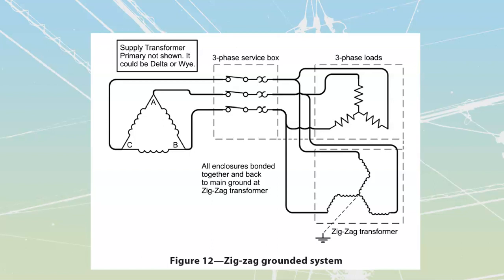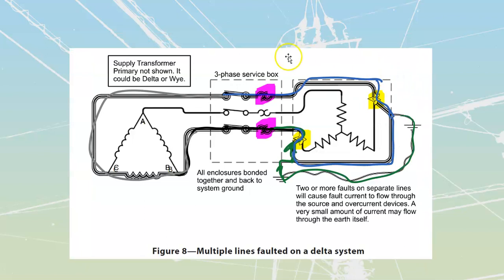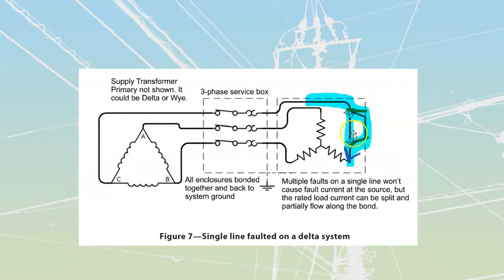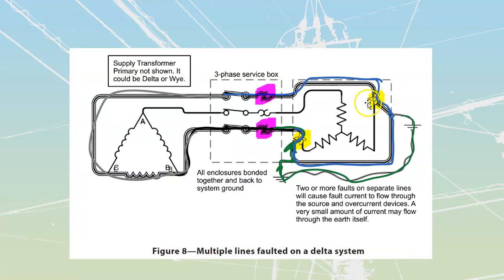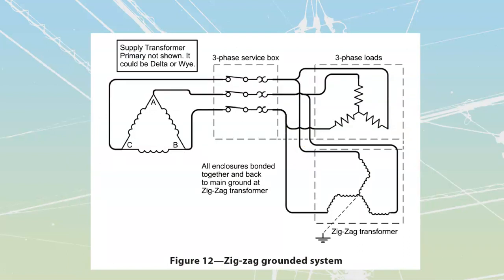Remember how with the delta system before, we said we had to have two faults before a fault current could develop all the way through. If only a single line was faulted, it wouldn't trip anything—no excess current created, just maybe a bit split along the bond, which is illegal but not the end of the world compared to other options. Since we have to wait for two faults, that's playing pretty risky odds.